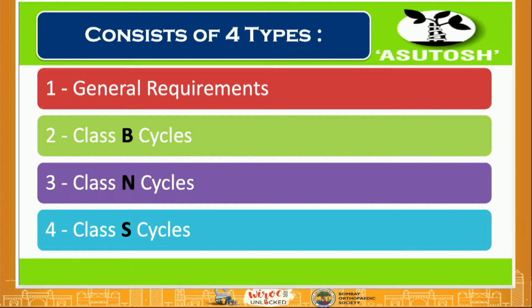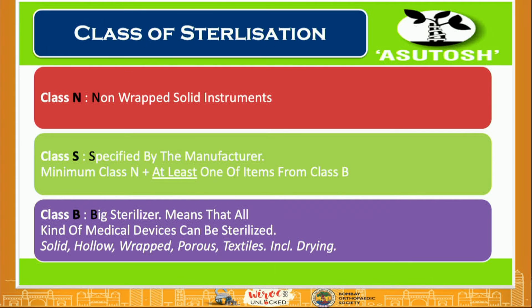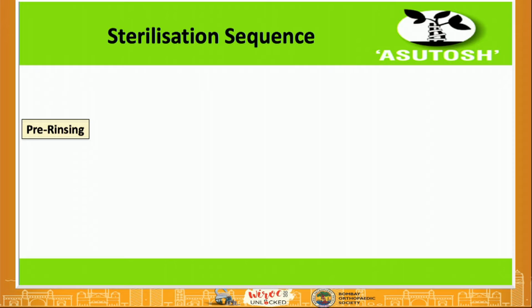Someone may ask you what cycle autoclave you are going to buy. So there are 3-4 cycles. There is a class B, N, and S. The N is for non-wrapped instruments. The S is what is specified by the manufacturer, and B is the usual, the big sterilizer that we use. So if you have a B category of sterilization, probably it covers all our requirements.